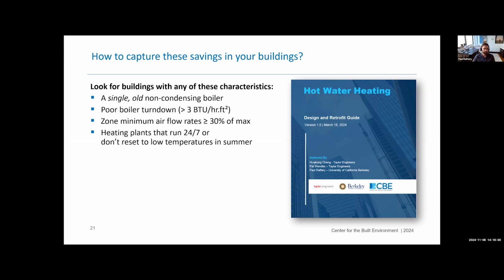just through controls measures. On the heating plant side, if you see these heating systems that are running 24/7 because somebody 20 years ago heard about a leak in another building, but then ran the hot water system 24 hours a day, then there's also a good opportunity to reduce waste there. Same goes for the temperatures not resetting, especially in summer months. If you still have the same temperature water as you had in the winter, there's a lot of energy waste happening there. And that's true regardless of whether it's a district hot water system or steam system or a dedicated boiler plant in the building. There's still a lot of waste happening.